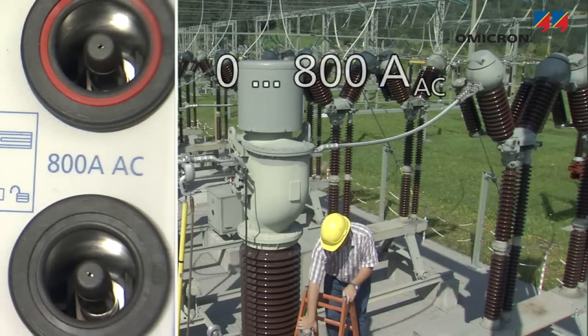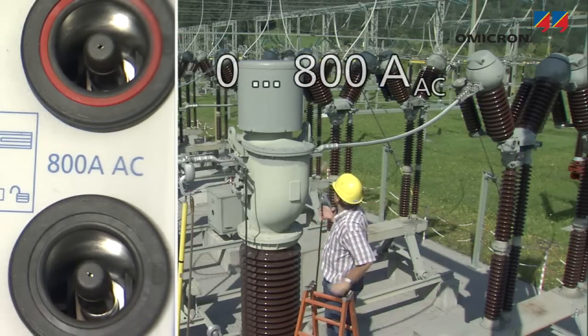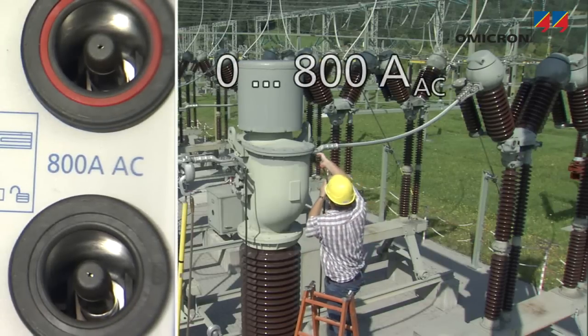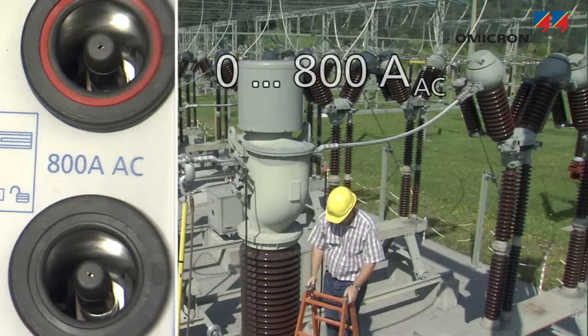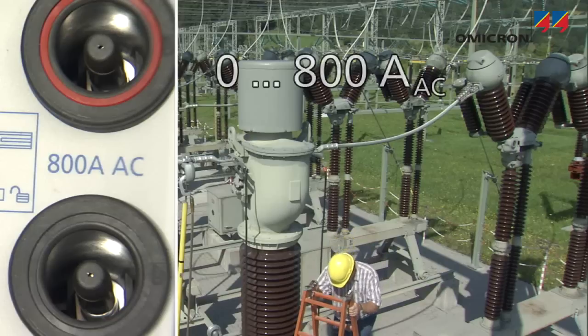The 800 amp high current output is mainly intended for testing current transformers. The CPC also verifies the CT's polarity by comparing the phase angles of primary and secondary current.